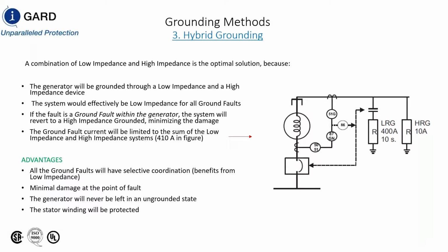How did you account for failure of switching device, contactor, on generator LRG resistor? Well, proper maintenance. You'll always have to exercise these contactors and make sure that they're functional. Everything is going to depend on maintenance. Even if these are reputable devices that we put in, they require maintenance or exercising, much like you would have to exercise the breakers. So nothing is going to be a substitute for maintenance and ensure that everything works when it's supposed to work. On the same token, you have to calibrate all your 87 relays and make sure that they're functional. Maintenance is paramount to almost everything else.